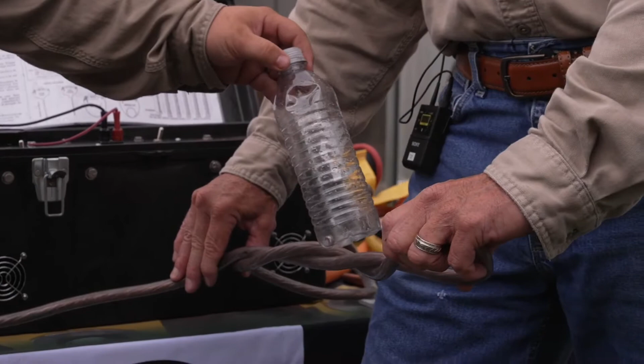Here in a tight parallel, this is going to represent a ground in a straight line out in the field. Since our tester is obviously a compact unit, we can't test them in a straight line, but we can put them in a tight parallel. So you see there's a lot less magnetic activity. That shows how the magnetic field's offset, giving you an example of why you want to use your grounds in a straight line if possible. All right, everybody see that?